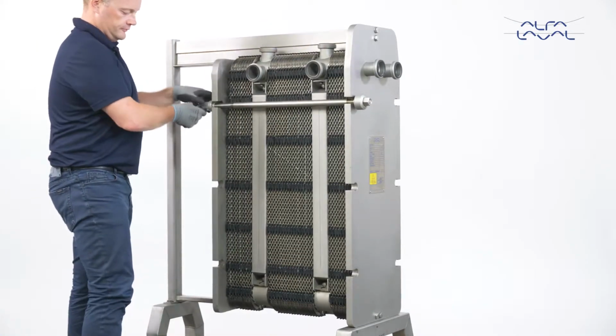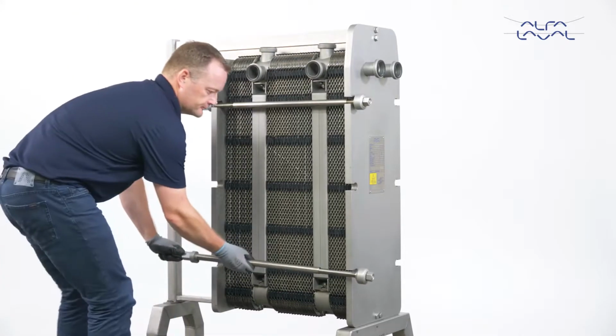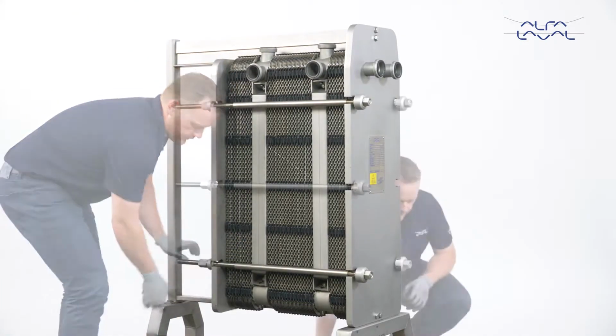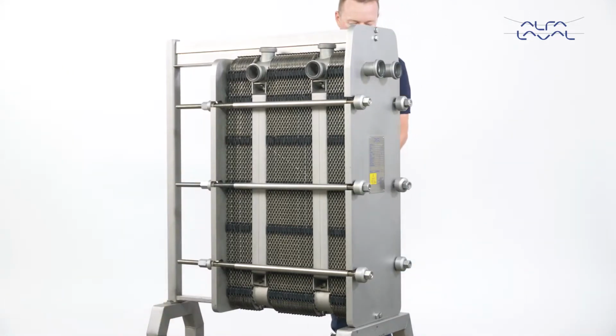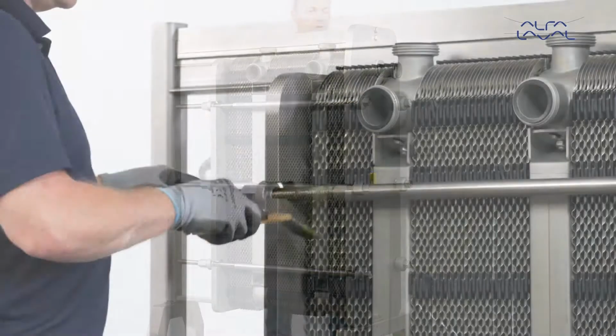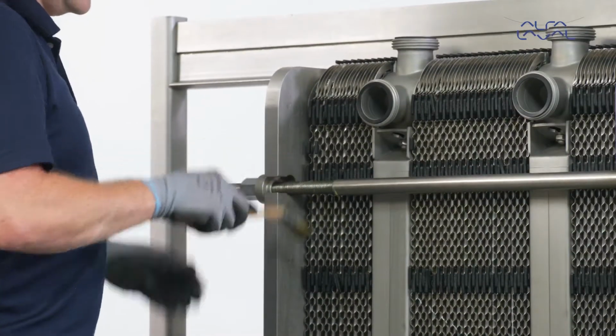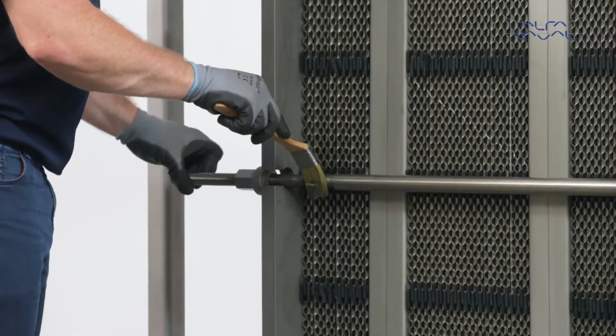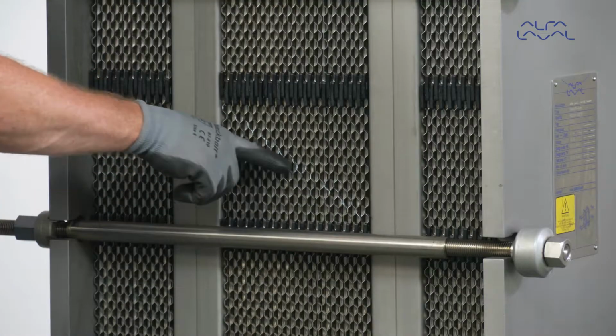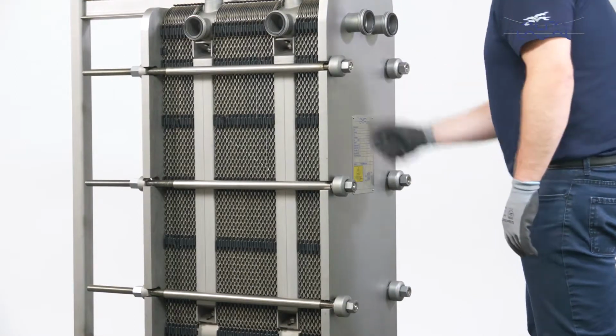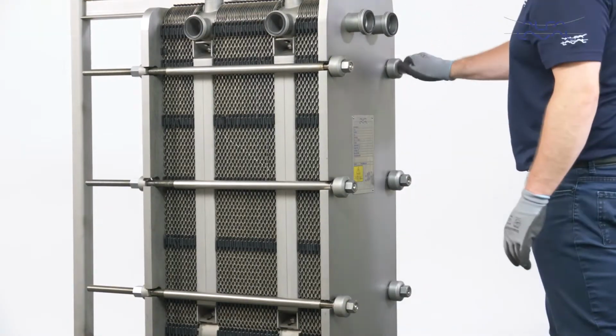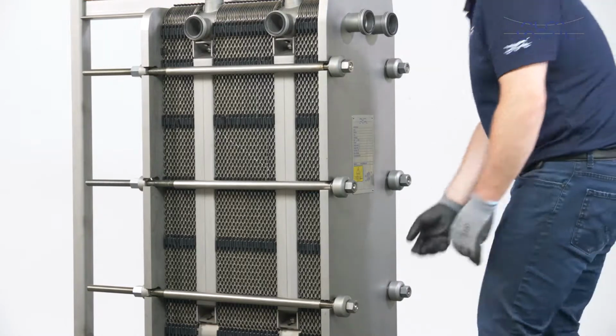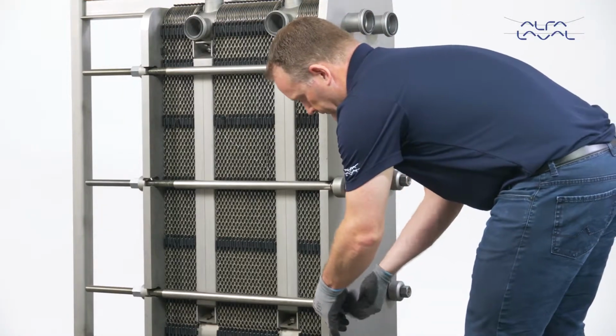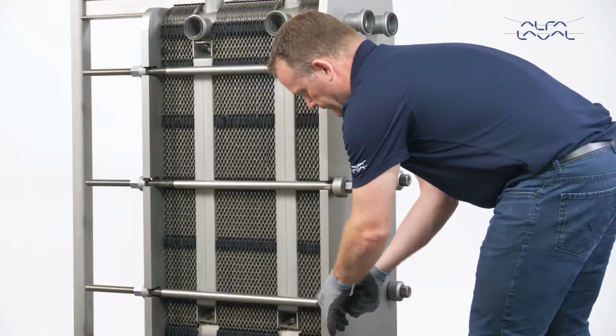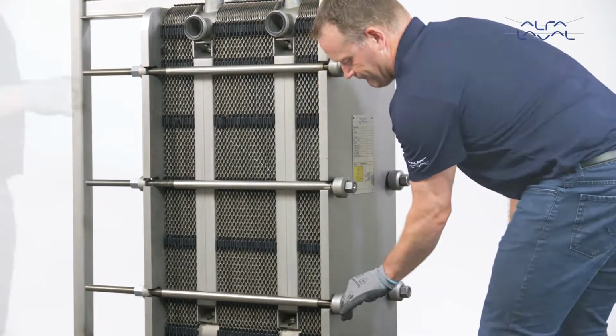First, press the plate pack together and insert the 4 tightening bolts and the locking bolts. Make sure the threads are greased. Check the marked line that has been made when the plate heat exchanger was open. Tighten the 4 tightening bolts in sequential order: 1, 2, 3, 4, as shown. Continue to tighten them until the reaction force on the plate pack can be noticed.